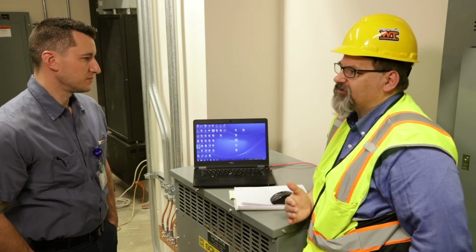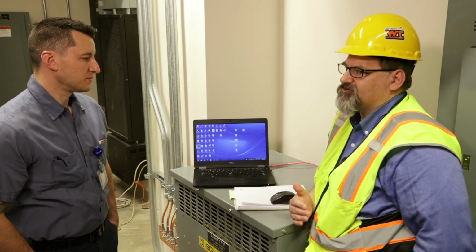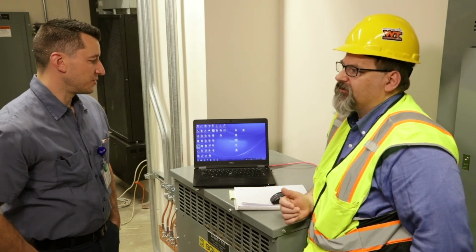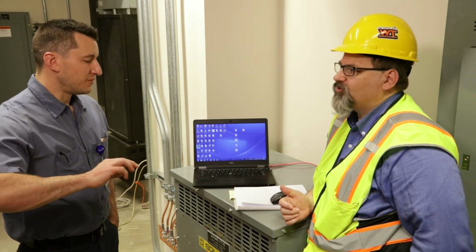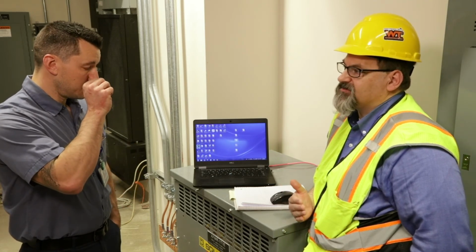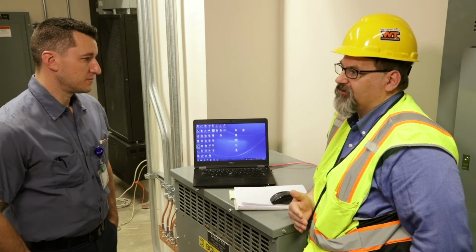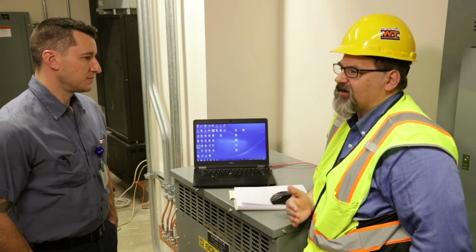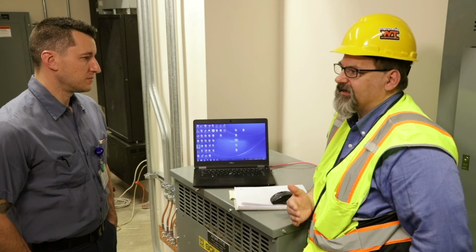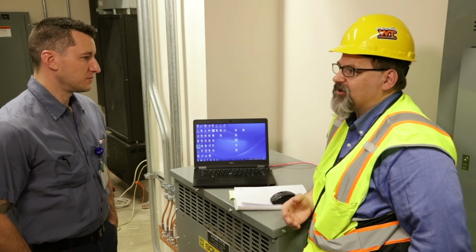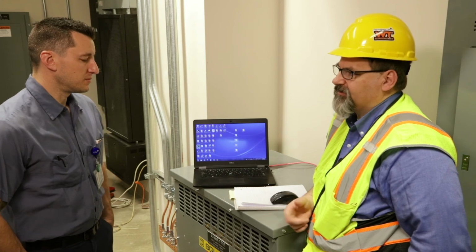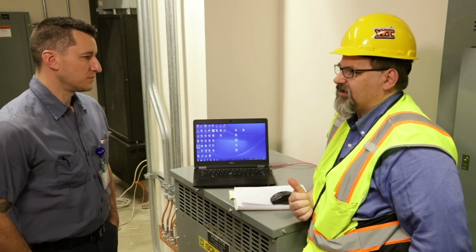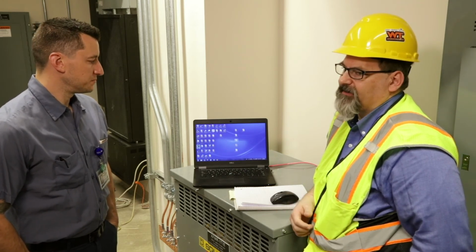But essentially, those plug load controllers listen to the occupancy sensors in the room, and they know if it's occupied, and that's when they turn on and off. And is that regardless of, you said most of the lights in the room are manual? Right? You could go in there, the occupancy sensor knows that you're in there. You could turn off the loads, and unless we've programmed the plug load controller to go with the lights, like in certain cases, we've done that because the plug load controller is not actually controlling an outlet, it's controlling a light in certain cases in this building, like an under-counter light.